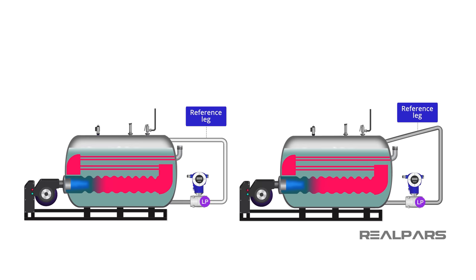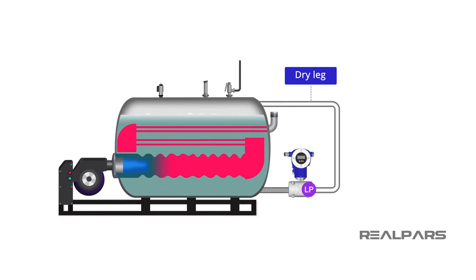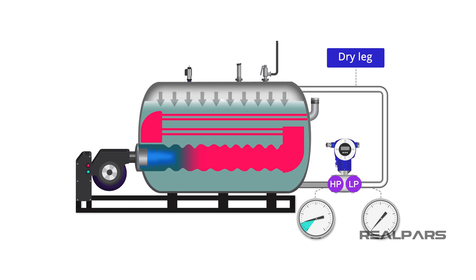The reference leg may be dry or filled with liquid. If the reference leg is dry, it is commonly referred to as a dry leg, and if the leg is filled, it is commonly referred to as a wet leg. In a dry leg system, the vapor pressure is applied to both the high pressure and the low pressure sides of the differential pressure transmitter. The same pressure applied on each side basically cancels each other out.